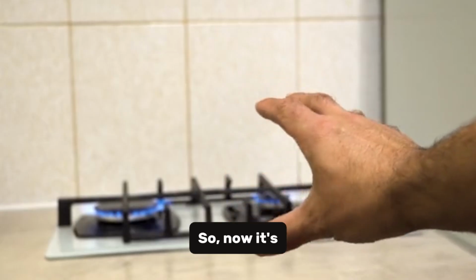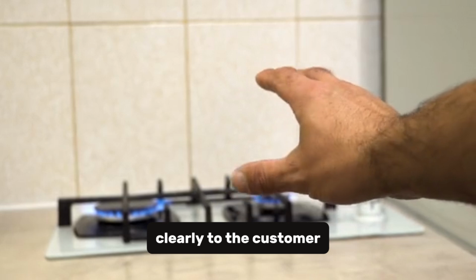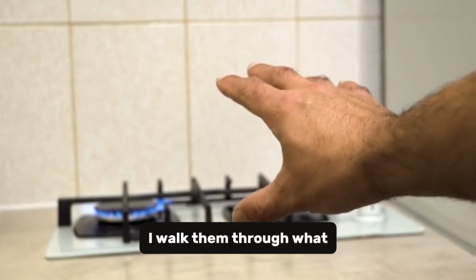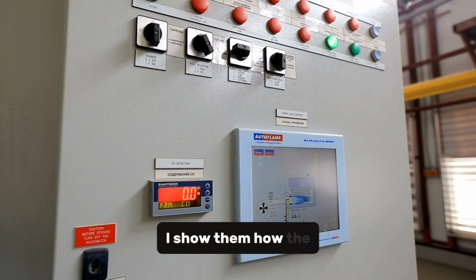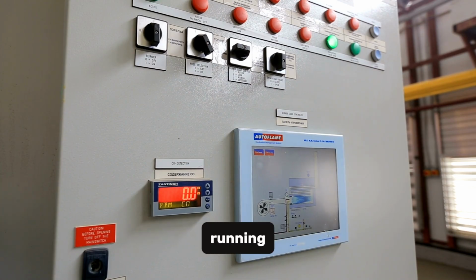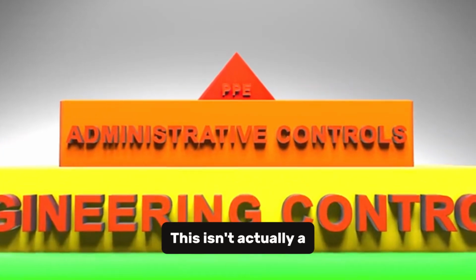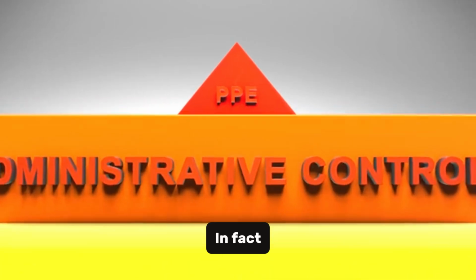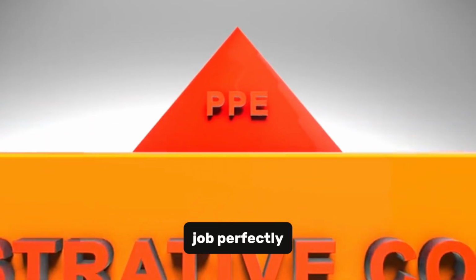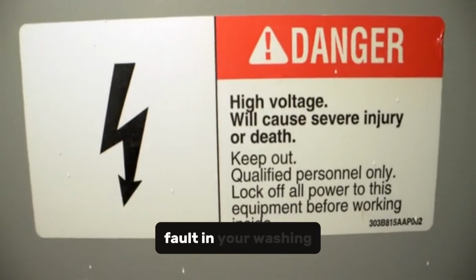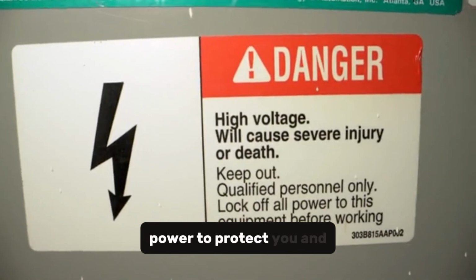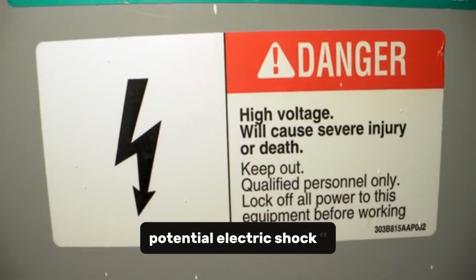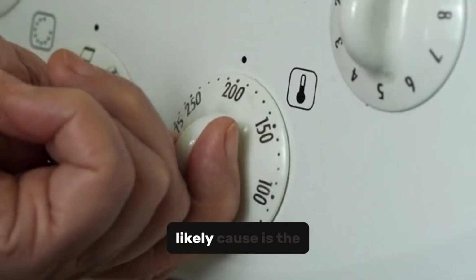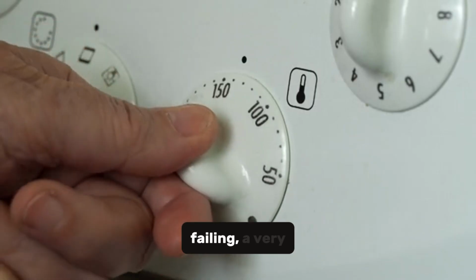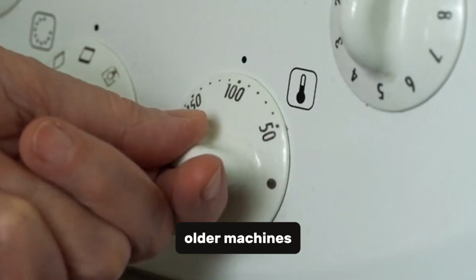So now, it's time to explain everything clearly to the customer. I walk them through what I've found. I show them how the circuits are fine, and how the RCD only trips when the washing machine is running. I explain, this isn't actually a problem with your fuse box. In fact, the RCD is doing its job perfectly. It's detecting a dangerous fault in your washing machine and cutting the power to protect you and your family from a potential electric shock. I let them know that the most likely cause is the heating element failing, a very common issue in older machines.